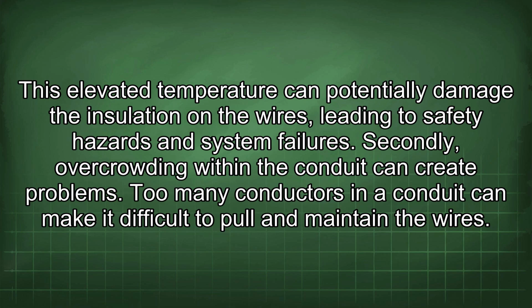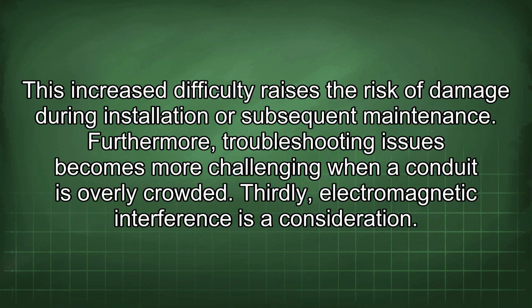Secondly, overcrowding within the conduit can create problems. Too many conductors in a conduit can make it difficult to pull and maintain the wires. This increased difficulty raises the risk of damage during installation or subsequent maintenance. Furthermore, troubleshooting issues becomes more challenging when a conduit is overly crowded.